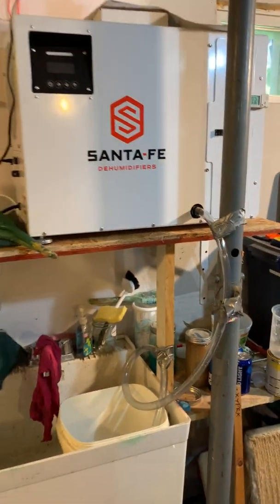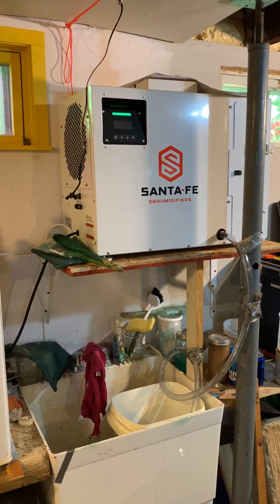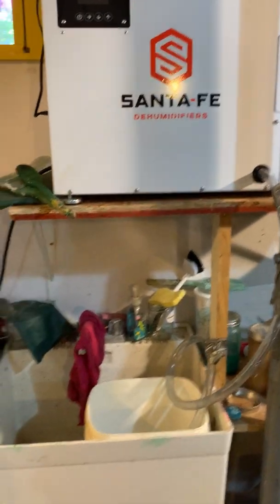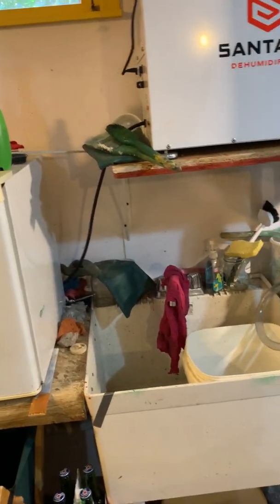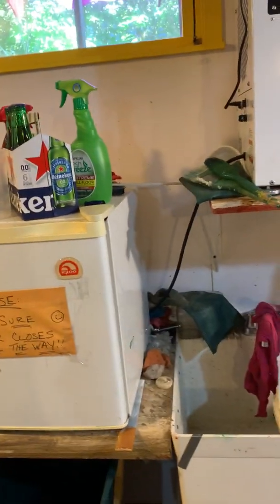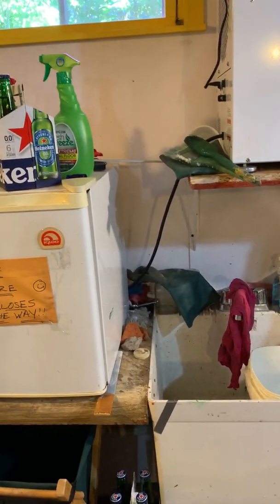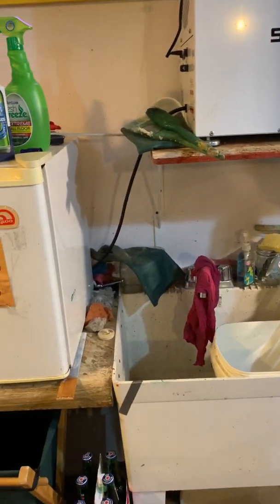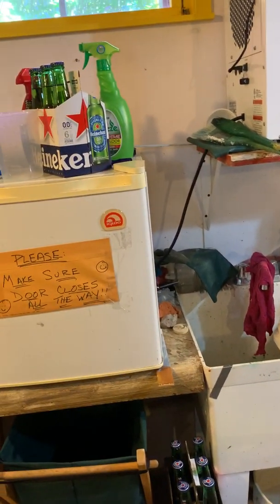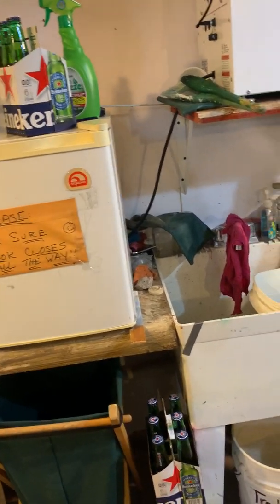And notice that I'm running a high-performance dehumidifier, a Santa Fe Advance 100 down here, in part because when we built the basement, we only had a little bit of dampness in the walls and they were wet. So I put in vapor-permeable spray foam insulation, vapor-permeable gypsum wallboard, and vapor-permeable paint, because I'm letting these walls continue to dry to the inside. Well, what does that mean? When they're drying to the inside, I'm getting moisture both through the slab, if there's no capillary breaker moisture barrier underneath it, or through the walls. So it turns out that because I'm letting that moisture in, letting these concrete walls and the rest of the assembly dry to the interior, I have a moisture load, and particularly in the summer.